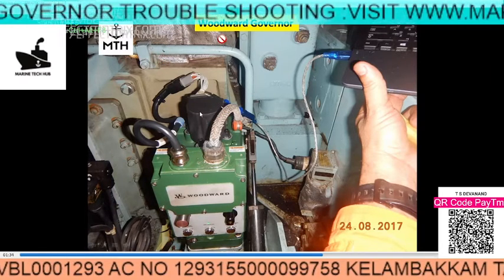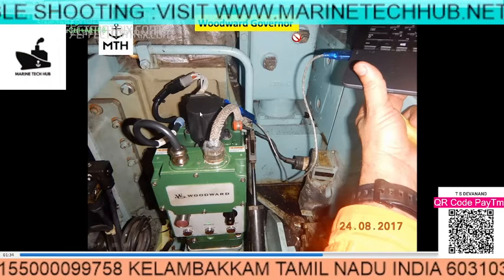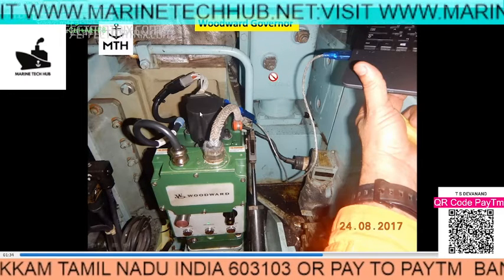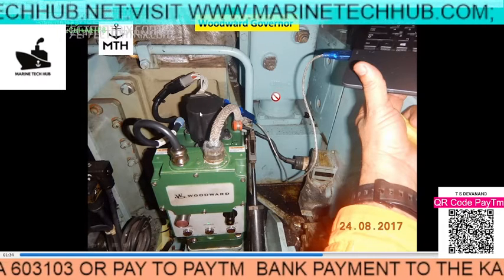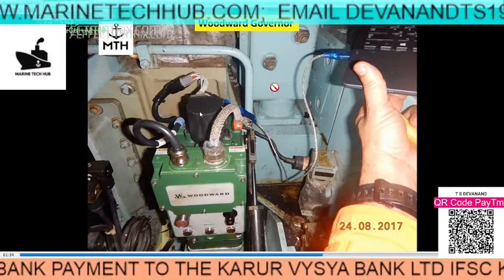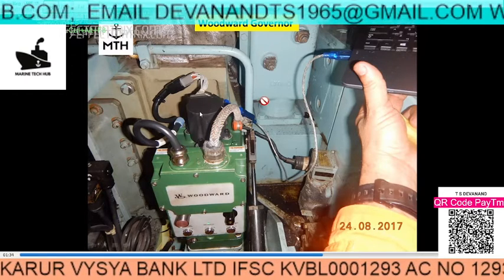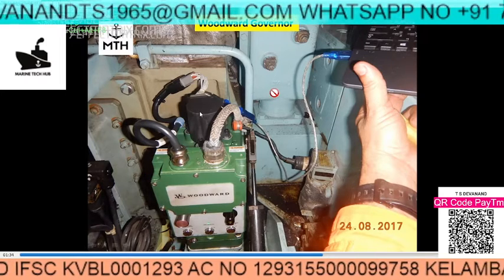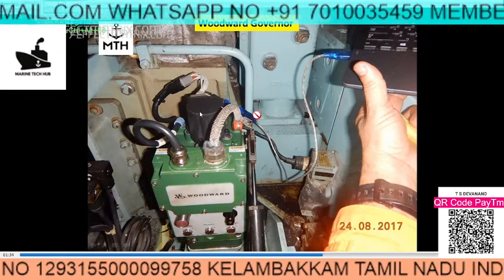Welcome to Marine Tech Hub. Today I will be explaining about the Woodward governor and what went wrong. One generator was running and we started another generator. After starting, we found the voltage was alright — 440 volts, everything was okay. We wanted to synchronize and put this generator in parallel, but while using the governor control to increase and decrease frequency, the frequency was not going up or down.